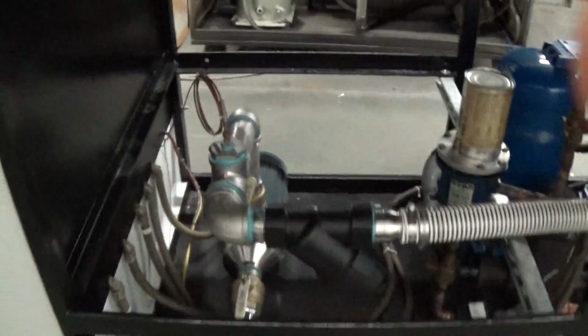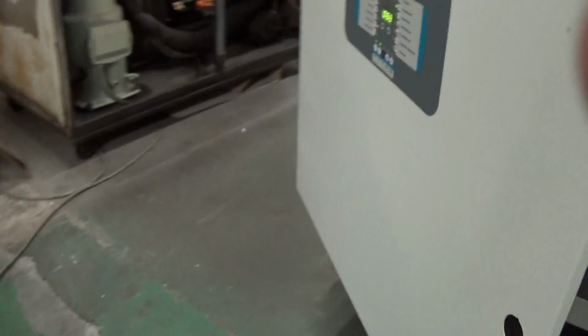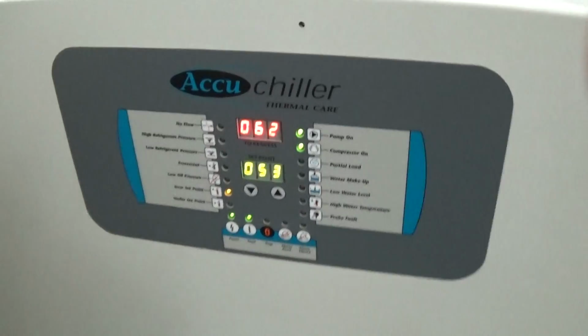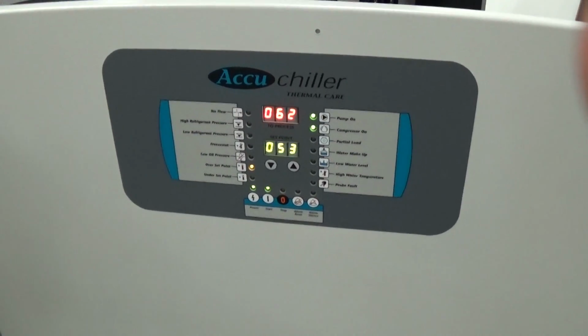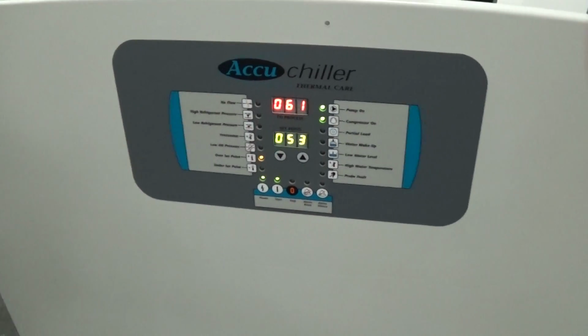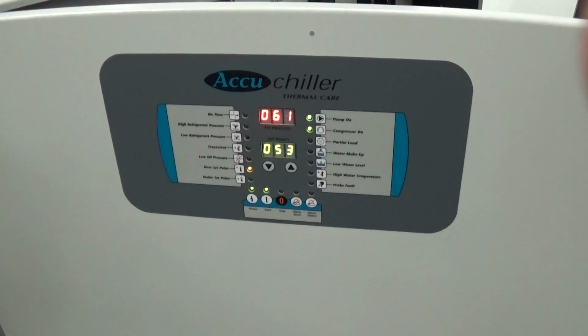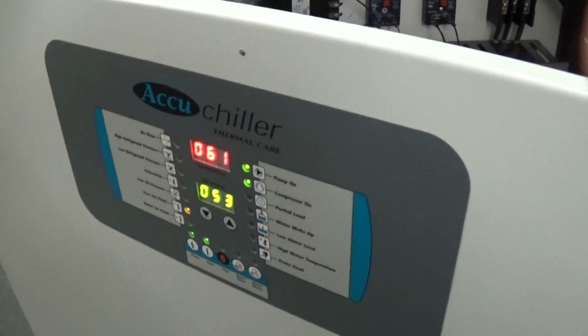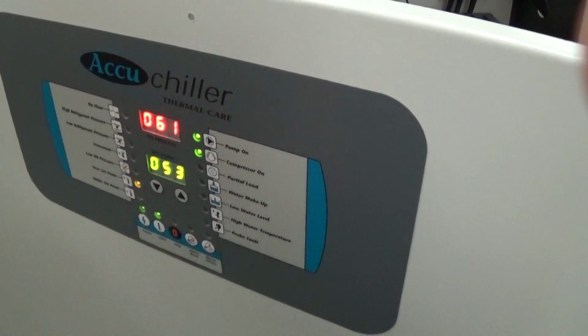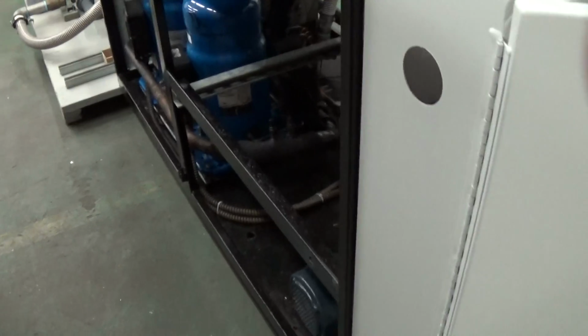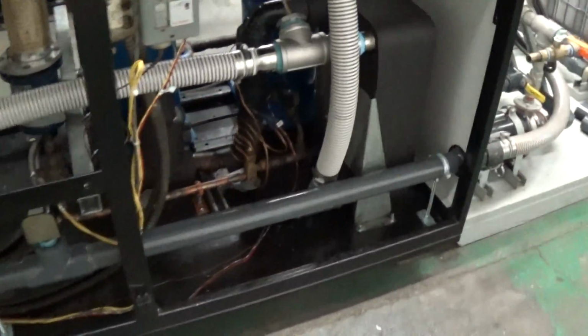This is controlled by that shut-off there. So this controller, embedded in this controller, it goes about 4 or 5 degrees below set point before it shuts off. Within that temperature range, the partial load or the hot gas bypass will be coming on and off. The hot gas bypass is basically that solenoid valve within the refrigerant circuit itself.